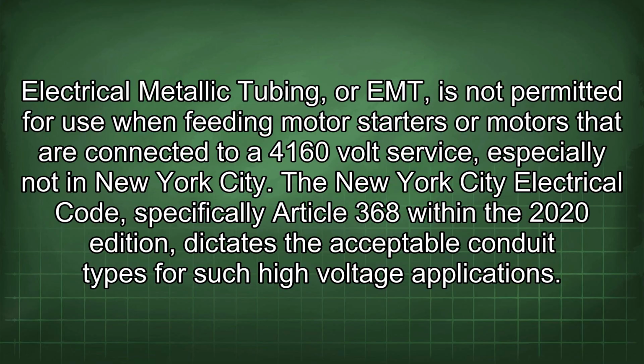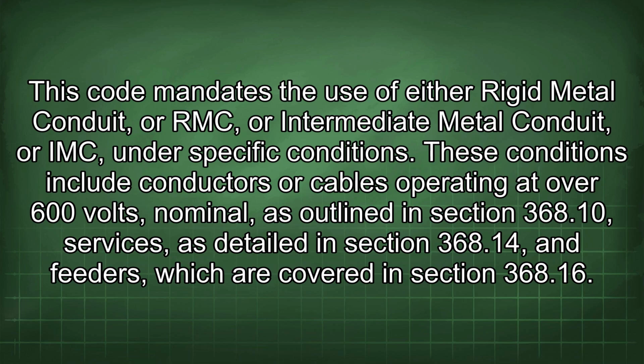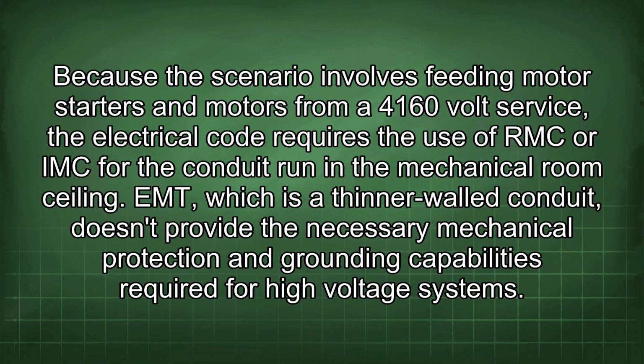high-voltage applications. This code mandates the use of either rigid metal conduit, or RMC, or intermediate metal conduit, or IMC, under specific conditions. These conditions include conductors or cables operating at over 600 volts, nominal, as outlined in Section 368.10, services, as detailed in Section 368.14, and feeders, which are covered in Section 368.16. Because the scenario involves feeding motor starters and motors from a 4160 volt service, the electrical code requires the use of RMC or IMC for the conduit run in the mechanical room ceiling.